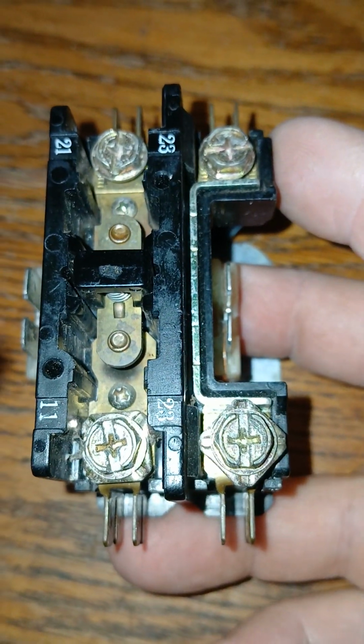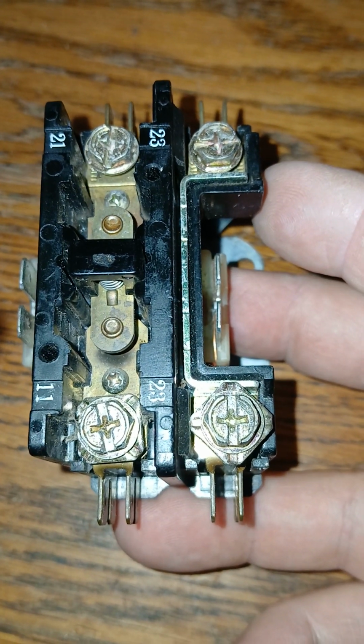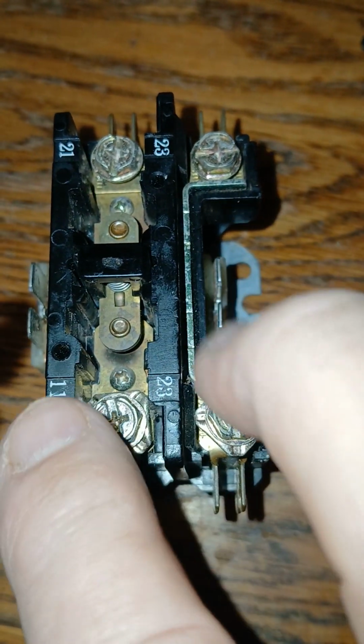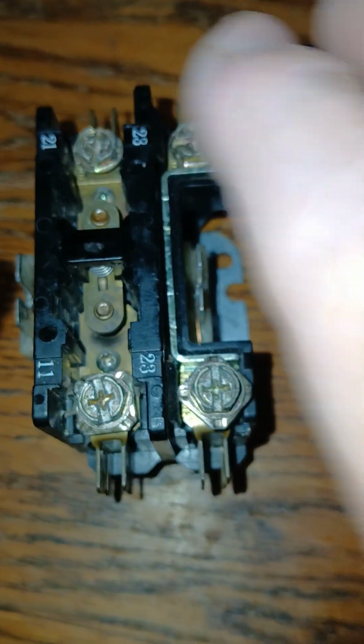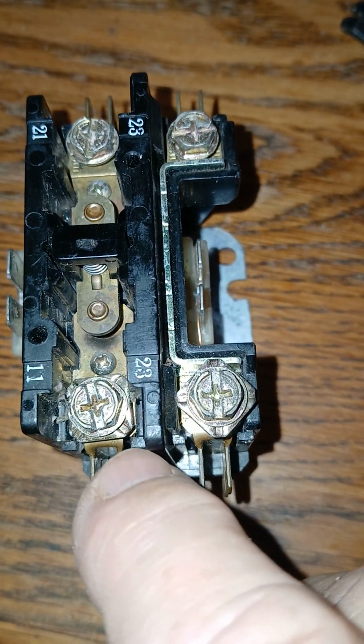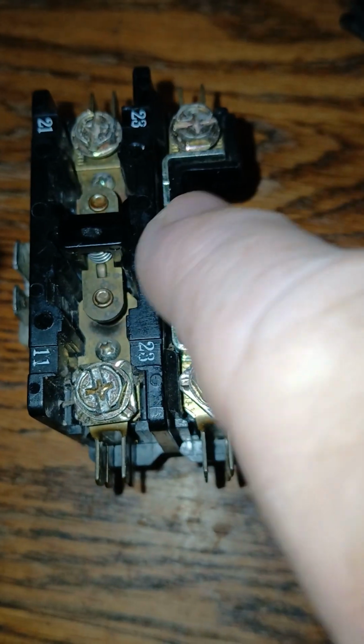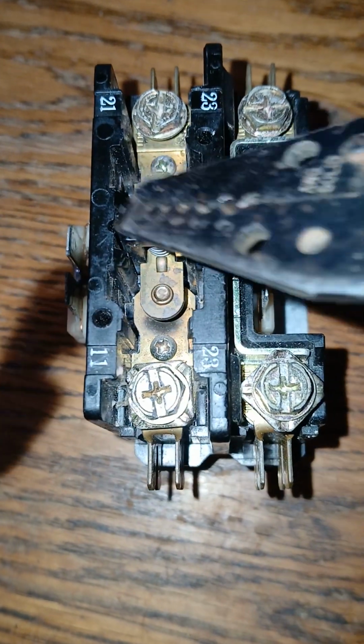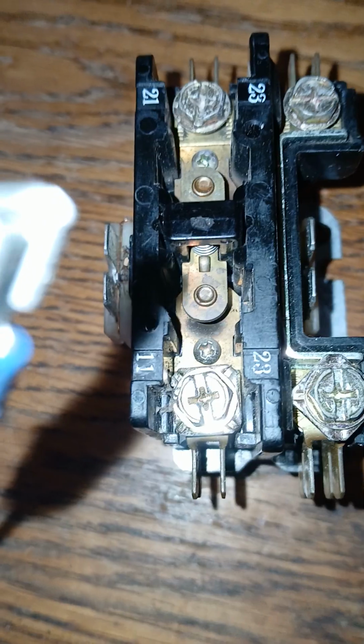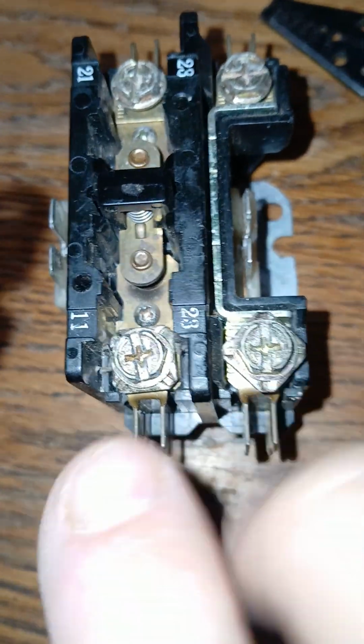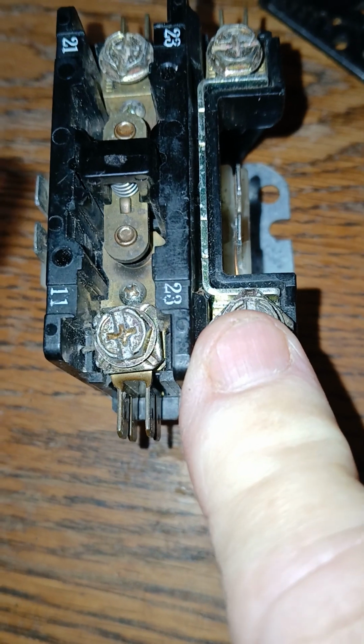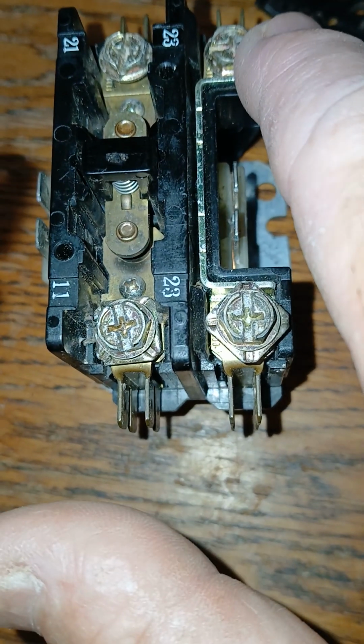Contactor for an HVAC, or heating and air conditioning, unit, namely to convey high voltage from one side to the other side, meaning that 120 here would jump to 120 here when the contactor is pulled in. This little gizmo here, as one can see, once this is pulled in. Now this can be done manually, but there would be 120 on this leg, 120 on this leg. So once the contactor's pulled in, this 120 jumps from here. So now you have 120 here, 120 here. 120 plus 120 is 240. 120 plus 120 is 240 here.